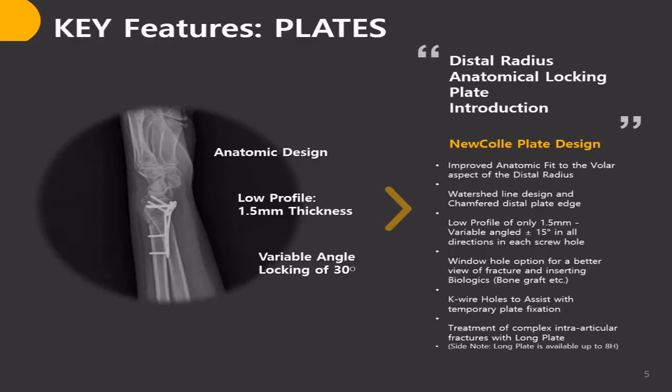The next two slides provide key features of NewColle, divided into implants and screws. Product features include: improved fit to the volar aspect of the distal radius; watershed line design and chamfered distal plate edge; low profile of only 1.5 mm; variable angle plus and minus 15 degrees in all directions in each screw hole; window hole option for a better view of fracture and inserting biologics; K-wire hole to assist with temporary plate fixation; and treatment of complex intra-articular fracture with long plates.